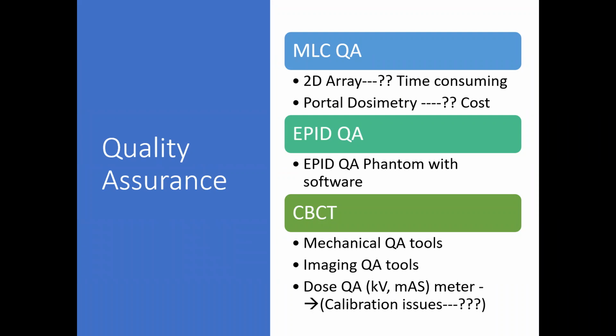You may need to buy certain imaging QA tools, and certainly we should perform a dose QA while measuring the kV and mAs values. There is always a problem with the dose QA of the CBCT. The meters being purchased have calibration issues, as we do not have any calibration laboratory in Pakistan. So every time we need to send these to the vendors, and it takes about 3 to 4 months to get them calibrated and returned after every 2 years, and it involves a lot of cost.